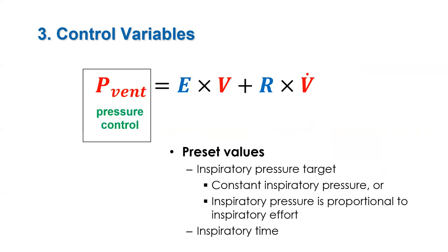The equation of motion is the theoretical basis for defining pressure control and volume control modes of mechanical ventilation. The ventilator can only control one side of the equation at a time. Pressure control means that the ventilator is controlling the left-hand side of the equation. That is, pressure is either maintained at a constant target value or it is automatically adjusted to be proportional to the patient's inspiratory effort. Changes in elastance and resistance cause changes in volume and flow.